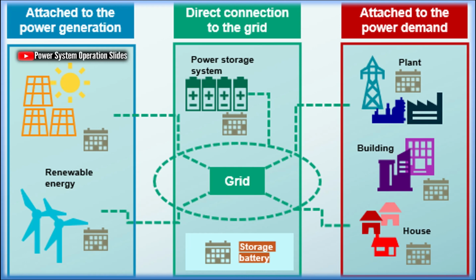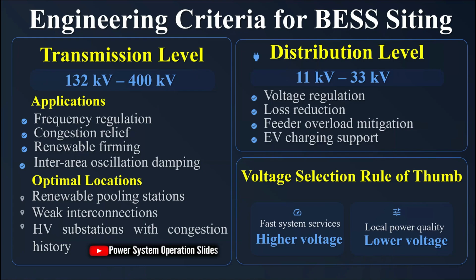Transmission-level BESS facilities are typically located near renewable pooling stations where multiple renewable resources connect to the grid, at weak interconnections between different transmission regions, or at high-voltage substations with a history of congestion. These locations maximize the BESS's ability to address system-wide challenges and enable the integration of additional renewable capacity without requiring transmission reinforcement.